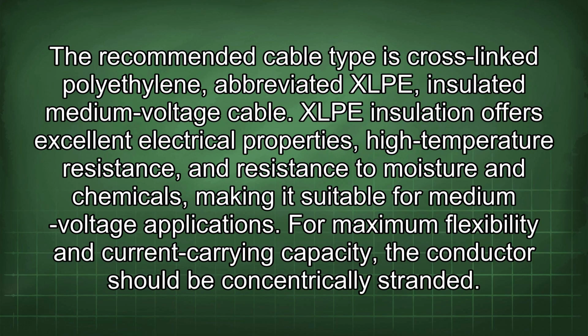The recommended cable type is cross-linked polyethylene, abbreviated XLPE, insulated medium voltage cable. XLPE insulation offers excellent electrical properties, high temperature resistance, and resistance to moisture and chemicals, making it suitable for medium voltage applications. For maximum flexibility and current carrying capacity, the conductor should be concentrically stranded.